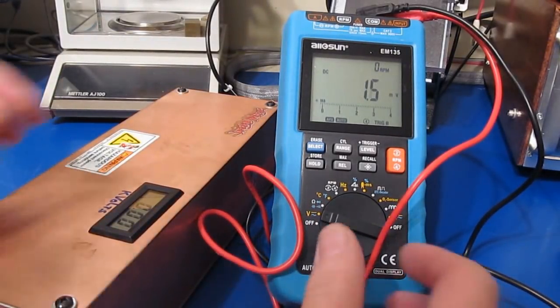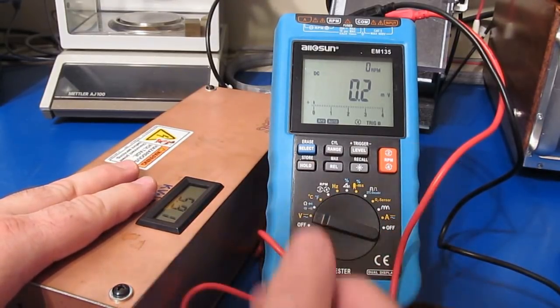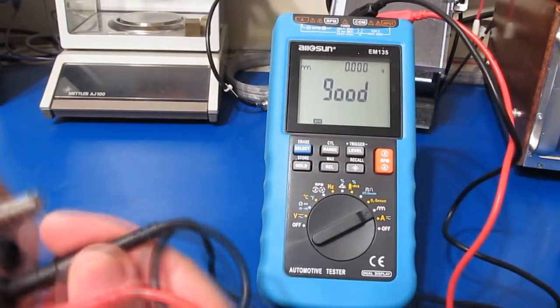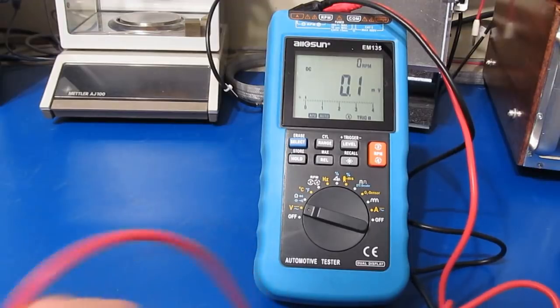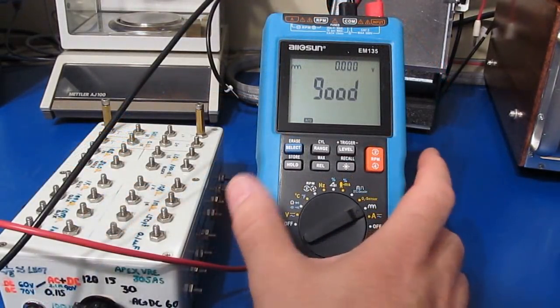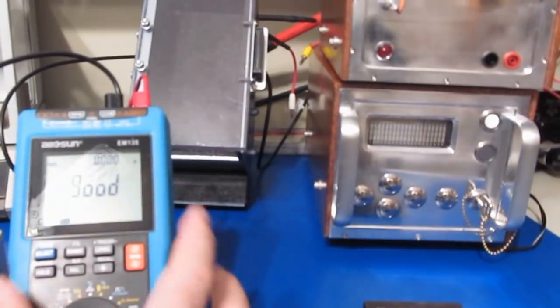Switching to pulse output allows the generator to mimic IEC standards. The plan is to apply five transients both positive and negative to see if this damages the meter. Testing proceeds through all inputs and reversing polarity. After functional testing, everything checks out fine.